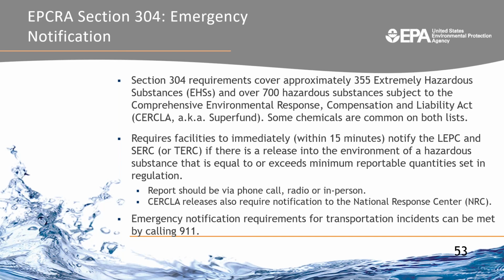And so Section 304 requires that facilities immediately, within 15 minutes, notify the LEPC and the SERC or the TERC if there's a release into the environment of a hazardous substance above quantities set in regulation. And this immediate report needs to be done over phone, radio, or in person. And then for the CERCLA releases, the Superfund releases, you must also notify the National Response Center. And emergency notification requirements for transportation incidents can be met by calling 911.